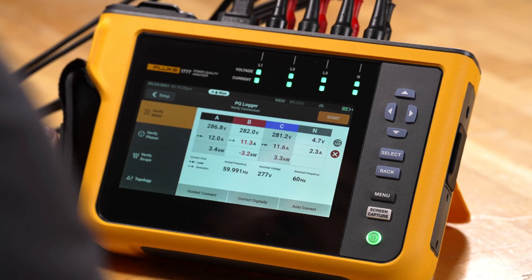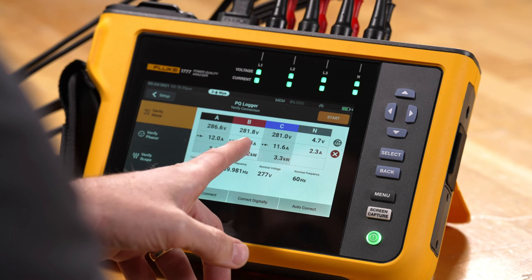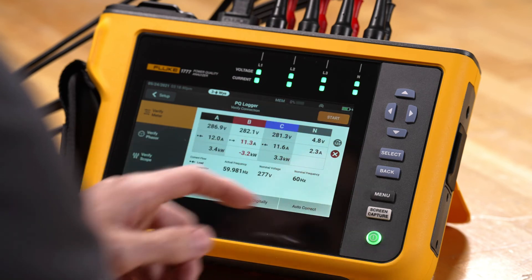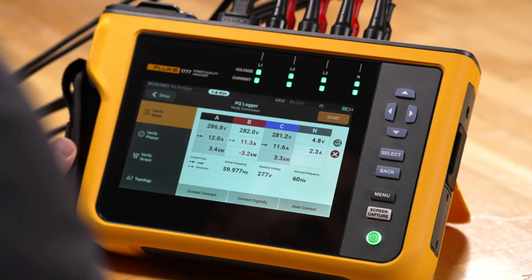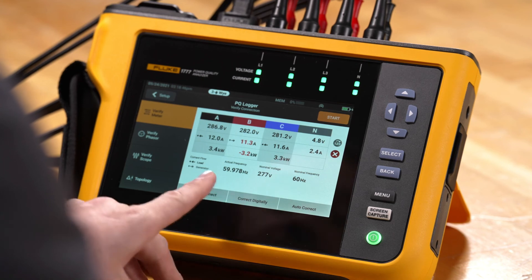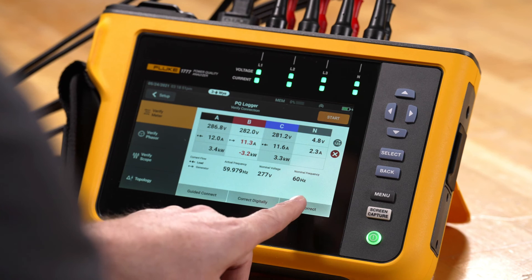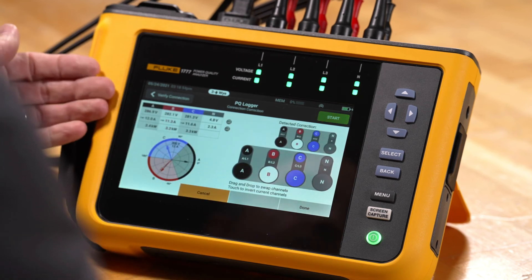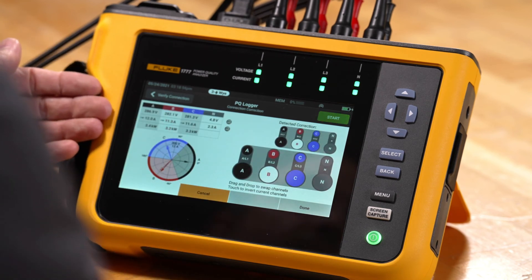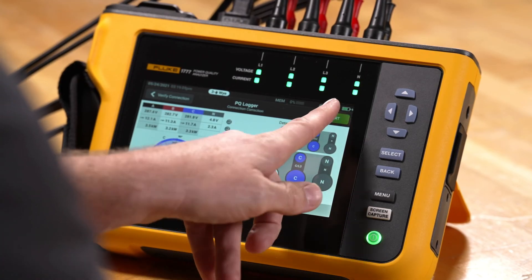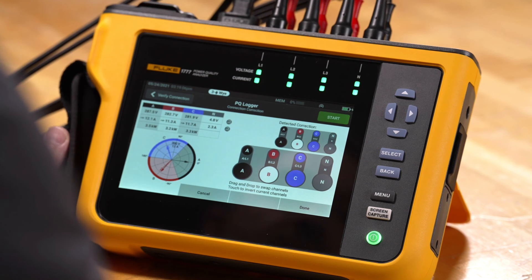Going back to Verify Meter, we'll see red indicators for the B phase — there's an X indication and an orange Start indicator, all telling us there's a problem with the current configuration. We have the option to correct digitally or we can do Autocorrect. By tapping Autocorrect, the meter will go through and fix itself and correct the problems, with no need to get back into the electrical panel. Now we'll see that Start is green, so we can tap Start to initiate the recording session.